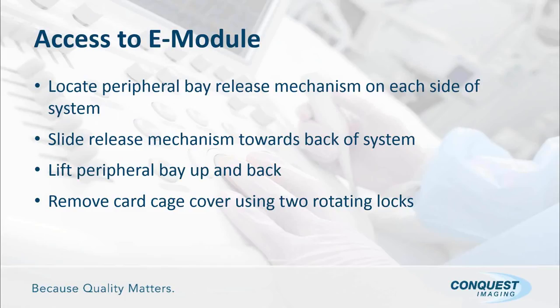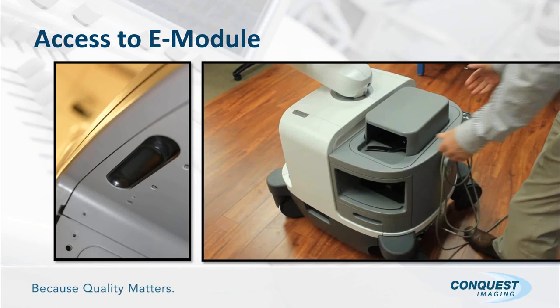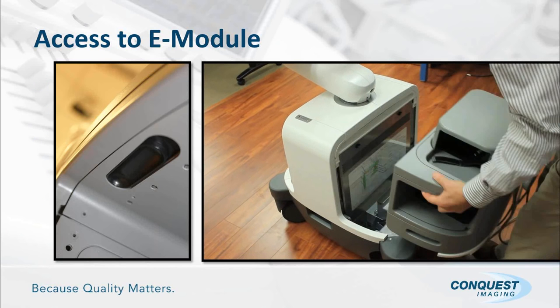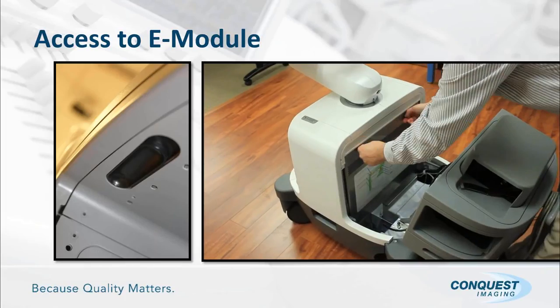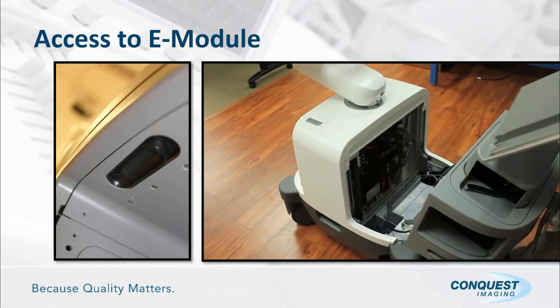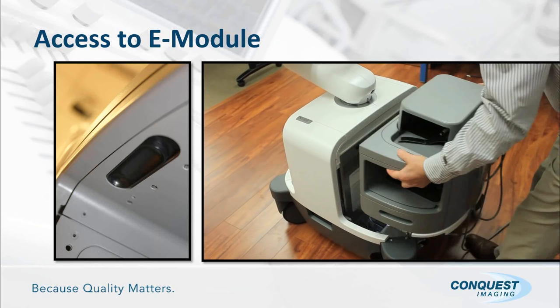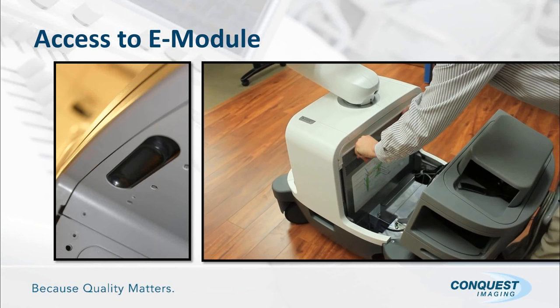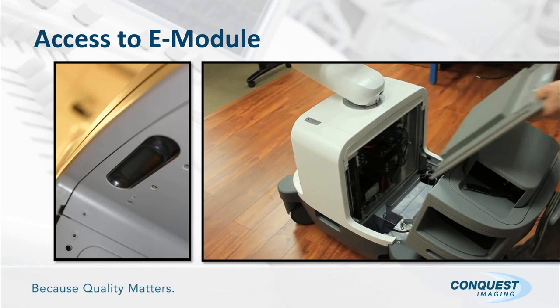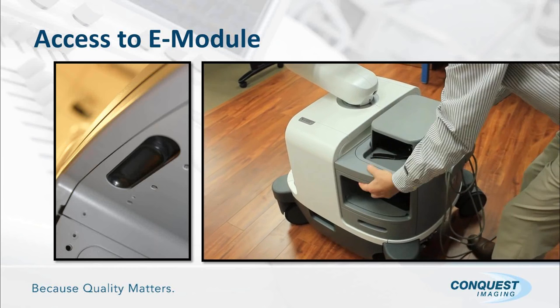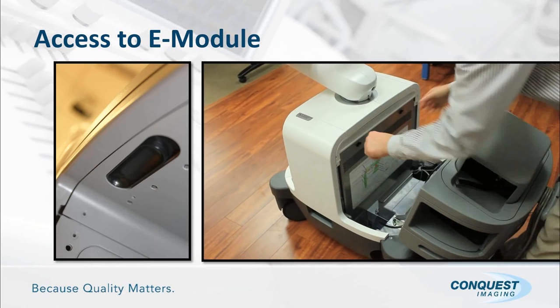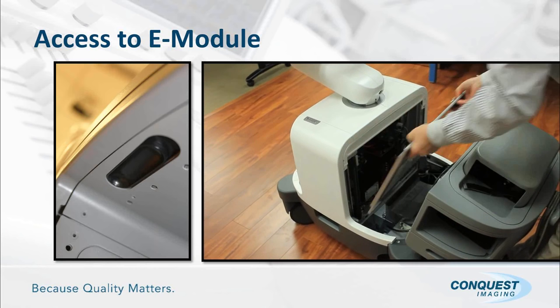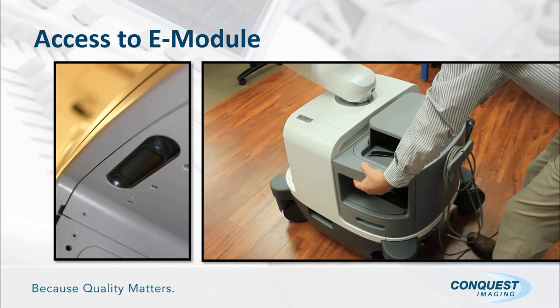And then you have your card cage cover that has two locks on it. These locks you just simply rotate 90 degrees and remove the E-module card cage cover. And here's a video of it. As I said, on the left, you can see the release mechanism, and there's a notch in there for your finger. You just hold it. Something I want to mention is there's one of these release mechanisms on each side of the system, and you may have an external I/O panel that's blocking or hiding the release mechanism on the left-hand side as you face the system from the front.